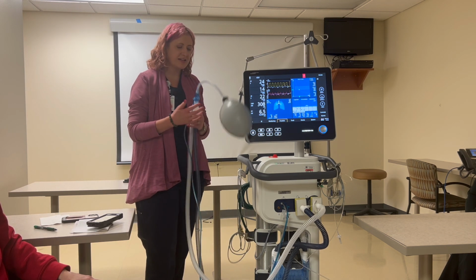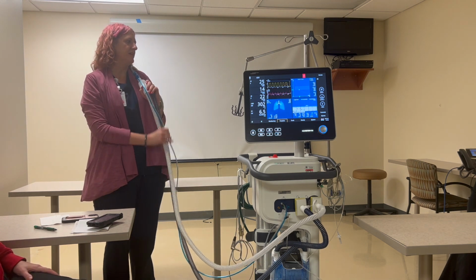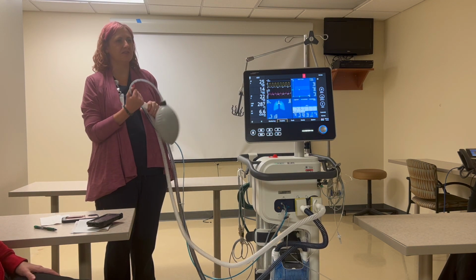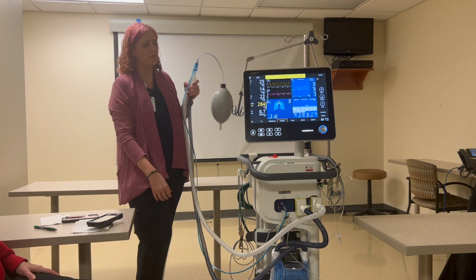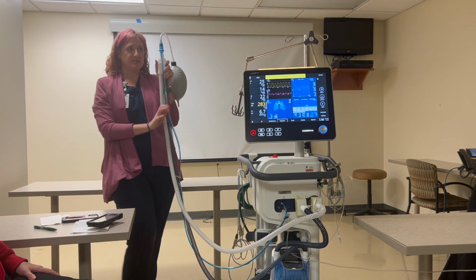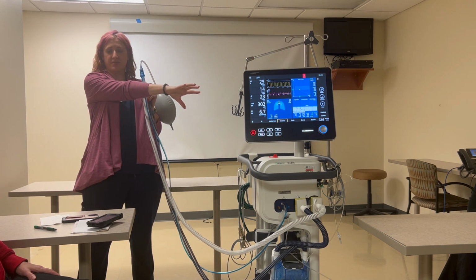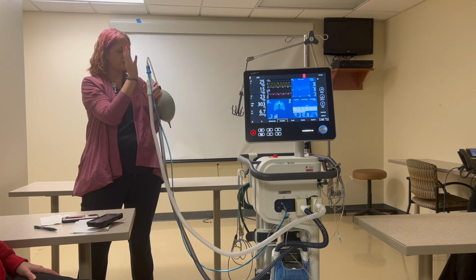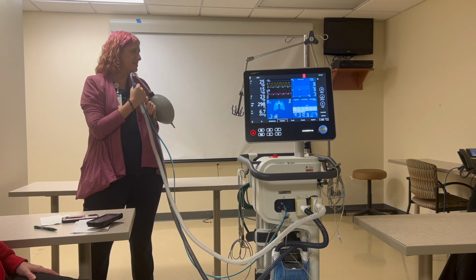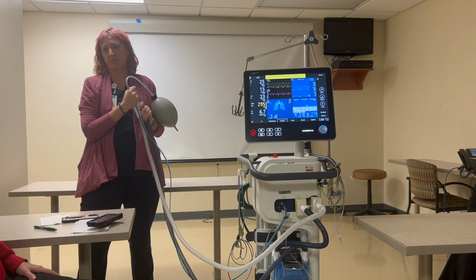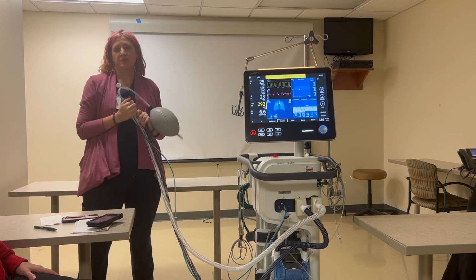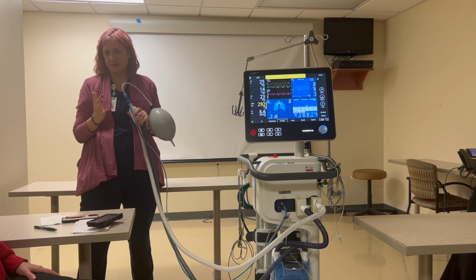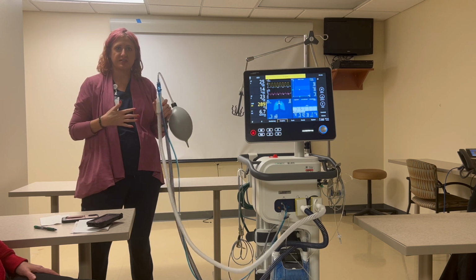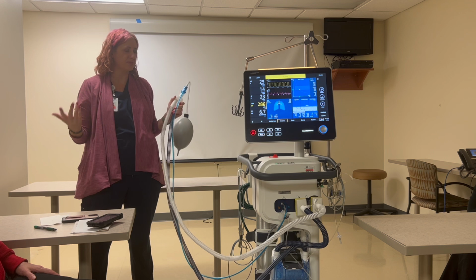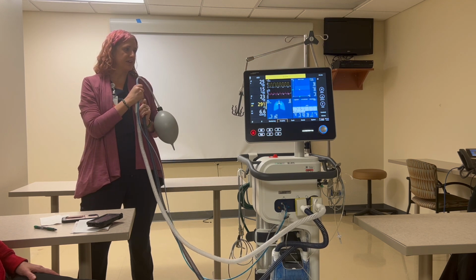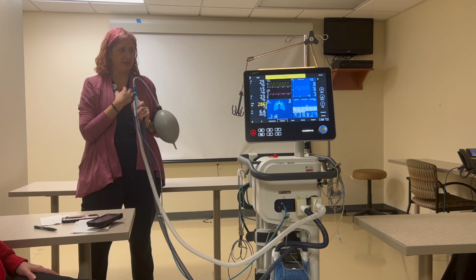The nice thing is, say you were moving a patient and you didn't notice that there was tons of water in here and then you flooded our flow sensor, and you can see water go into our flow sensor tubing. Yes, the ventilator is gonna alarm and tell you check flow sensor, and it's gonna give you a whole bunch of alarms. But if something ever happens to our flow sensor, like we drown it, we break it, we crack it, the ventilator will go into emergency backup settings. Those emergency backup settings are 15 centimeters of water pressure and it's just gonna keep the patient ventilating until we can figure out the problem or get a new flow sensor. So if you drown the circuit and my ventilator gets angry, your patient's still okay.